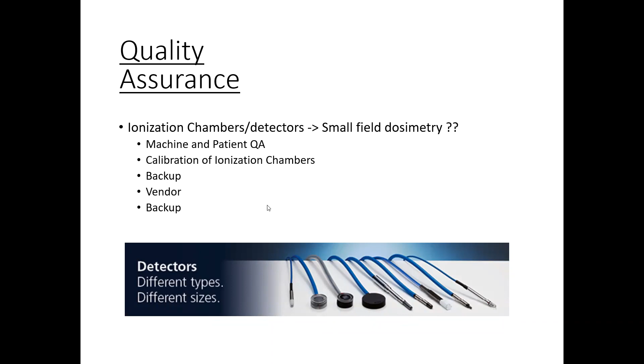If we are performing an MLC QA, do we need a 2D array or a portal dosimetry? There has always been a debate about that. So you can have a 2D array for the MLC QA, but certainly this is time consuming. You can have a license on your portal dosimeter, but that will cost you a little more than the 2D array. So you need to decide yourself about that. If you are performing MLC QA on a 2D array, this is an independent thing. This is one factor, but you are ending up with 45 minutes or 1 hour for an MLC QA on a 2D array. If you have portal dosimetry, you can perform your MLC QA maybe in 10 minutes, but this is a cost, and this is something which is not independent.